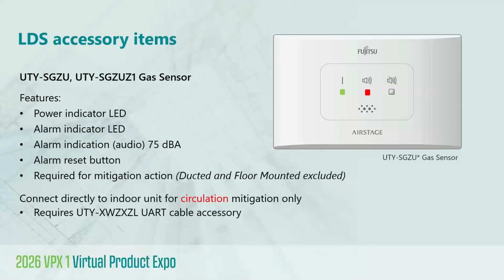But circulation is going to be used most often, which requires both the gas sensor that you see, and I'll say it once, but I'll refer to it from this point forward as the UART cable. That's the UTY-XWZXZL that you see in the bottom bullet. So the UART cable provides the connection between the gas sensor and the indoor unit UART port. But keep in mind, these components are, guess what? They're not required when using our ducted and floor-mounted units because, again, they have the factory installed gas sensor.